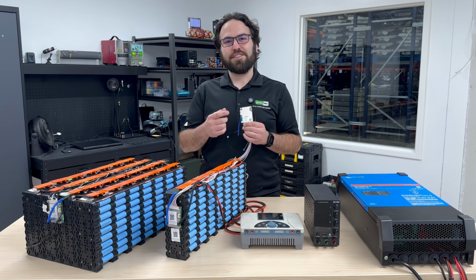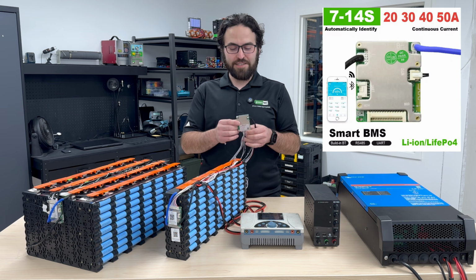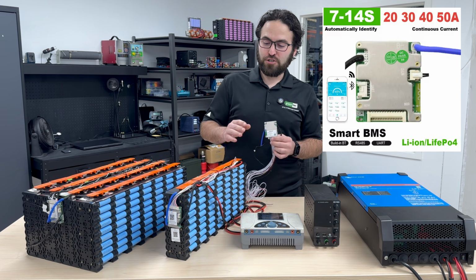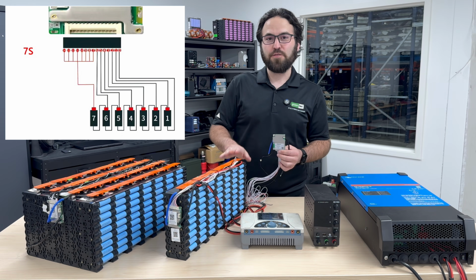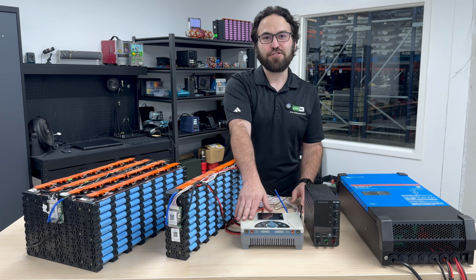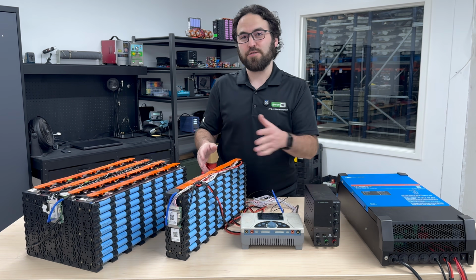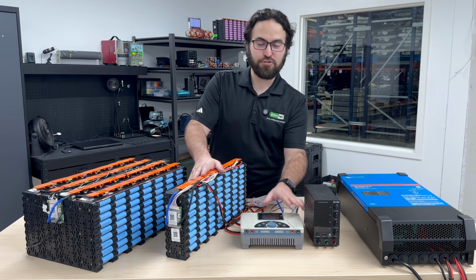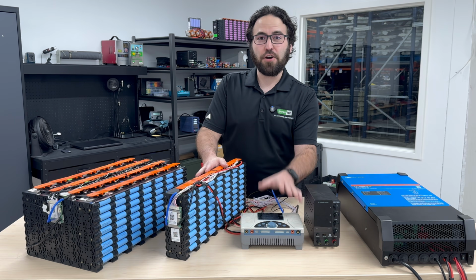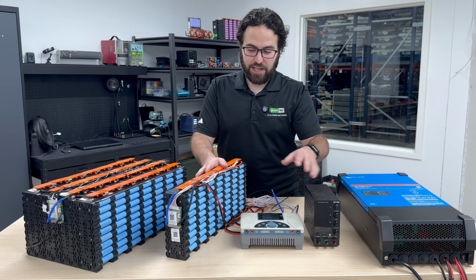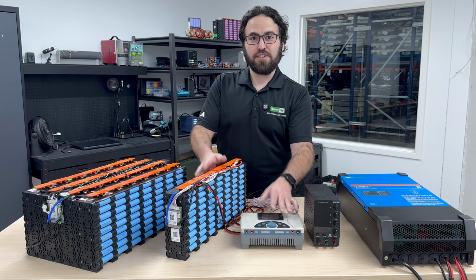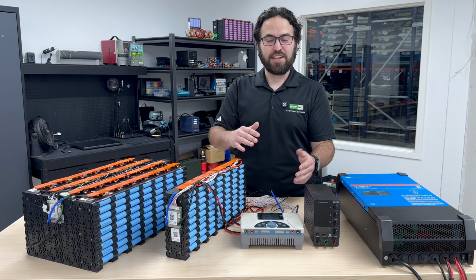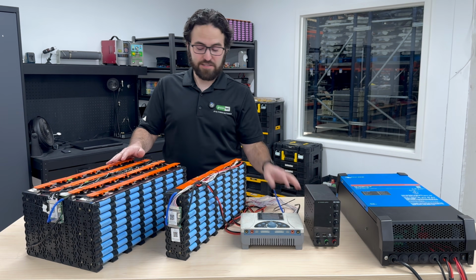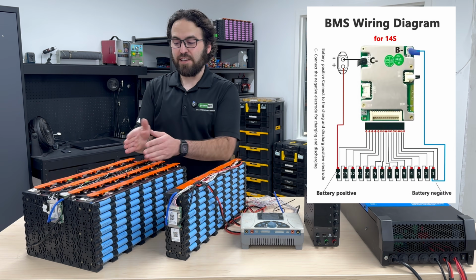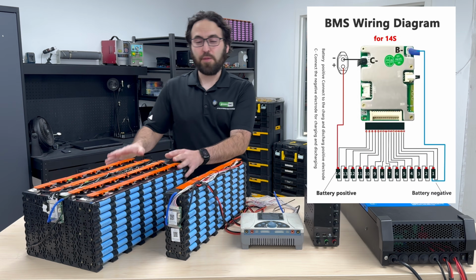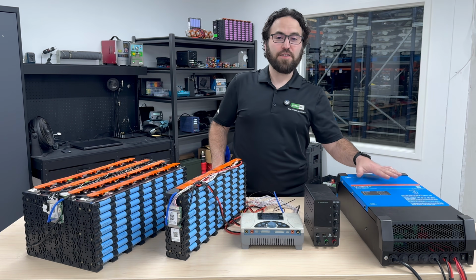Today I'm going to show you how to wire up this 50 amp continuous, 100 amp peak JBD BMS, a 7 to 14S BMS. I'll show you how to hook it up in a 7S configuration, which is 24 volts, to this eMatrix battery to power an iCharger, then use a DC power supply to assist as a UPS. Because this iCharger demands 40 amps, it will run off this battery uninterrupted, and the DC power supply will top the battery back up when it's not demanding that power, or in between charge and discharge cycles. I'll also show you how to wire the same BMS up in a 14S configuration, which is 48 volts, and then 2 more packs on the sides in parallel to double the capacity. I'll also demonstrate using this with a 48 volt inverter as well.